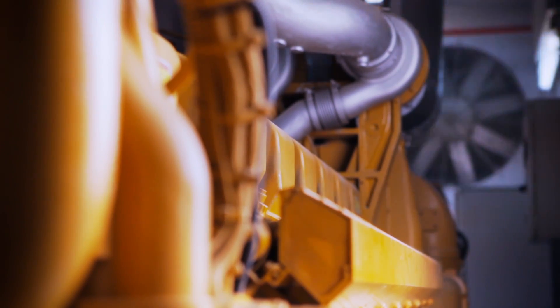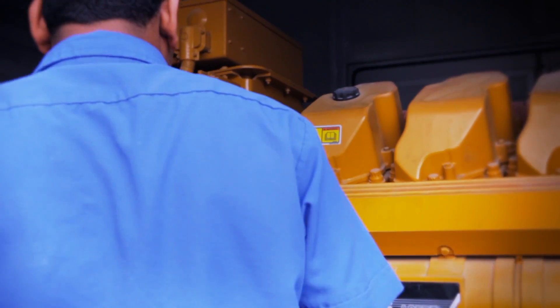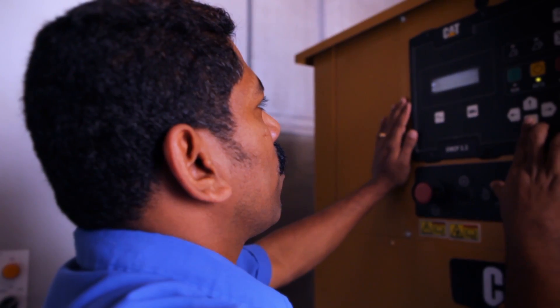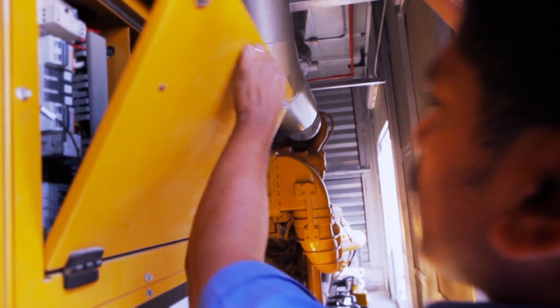To help provide continuous power generation in the event of an extended power outage, the C175 generator sets are combined with the CAT uninterruptible power supply system. The criticality comes in the startup and the stability of the generator — it should attain a certain speed and voltage to deliver the output in the prescribed time, which is fixed at 10 to 20 seconds.